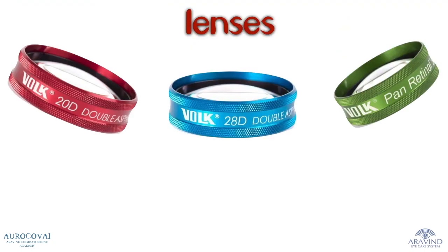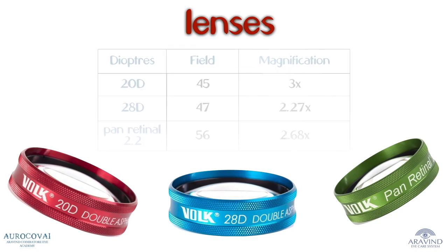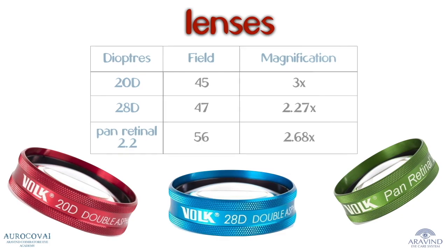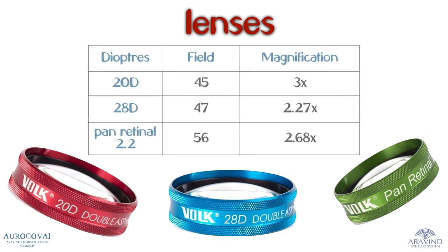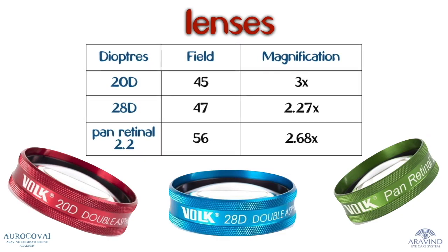Used in conjunction with the indirect ophthalmoscope are plano-convex condensing lenses. The most commonly used one is the 20 diopter lens, which has a magnification of three times and a field of 45 degrees. The 2.2 pan retinal lens and the 28 diopter lens are other commonly used lenses. The 28 diopter lens is ideal for an older population with small pupils and for neonates undergoing screening for retinopathy of prematurity.